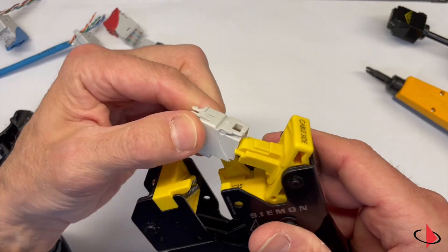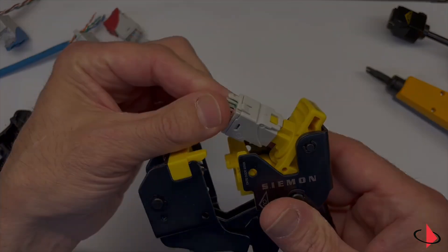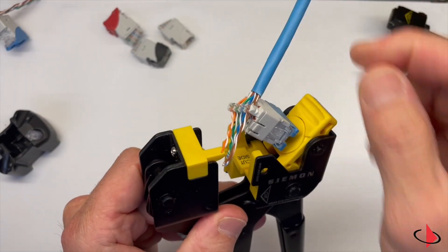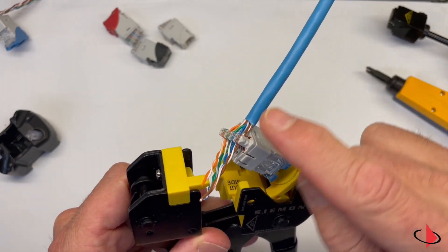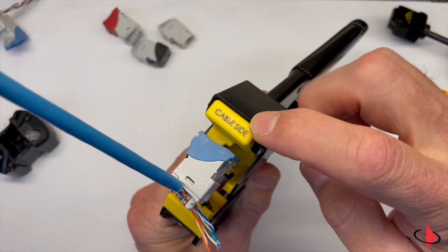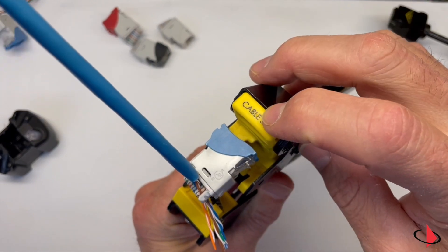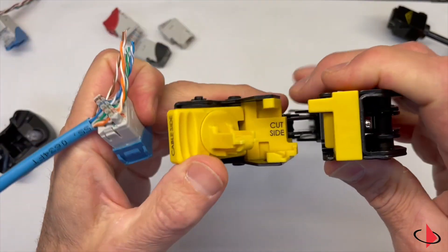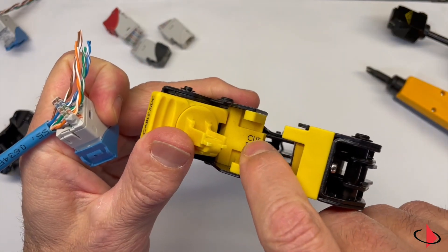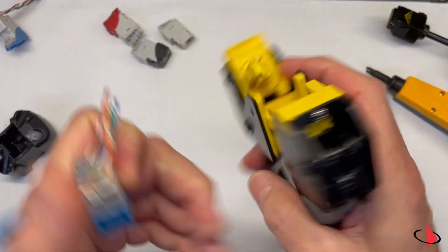With the cable laced into place, the outlet is loaded and rotated with the cable side here up as indicated by the text provided on top of the lever shown here. The conductors to be trimmed will then be in the correct position to be cut as indicated by the cut side text provided down in the lower portion of the tool. This is the same general location as the cutting blade.